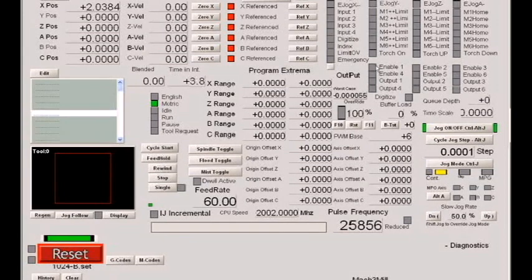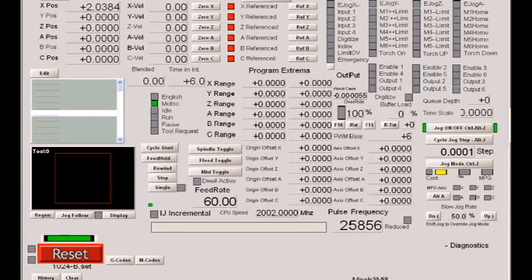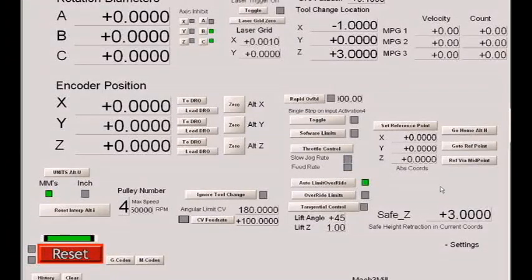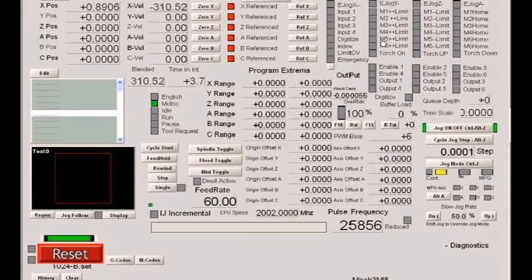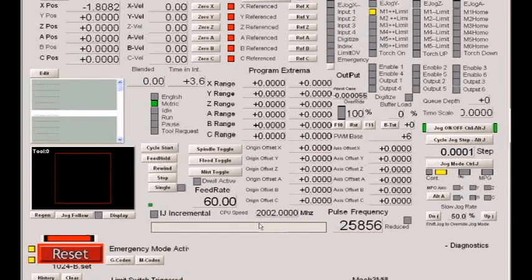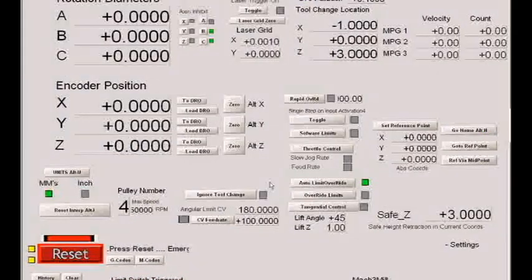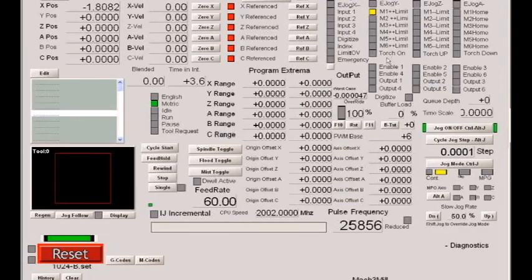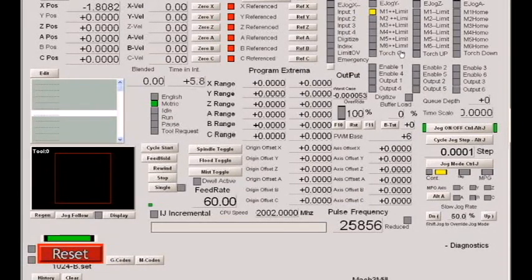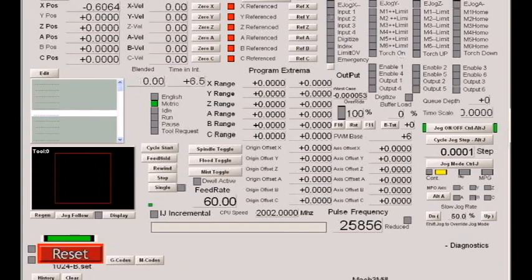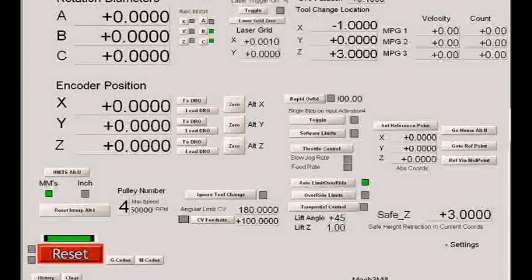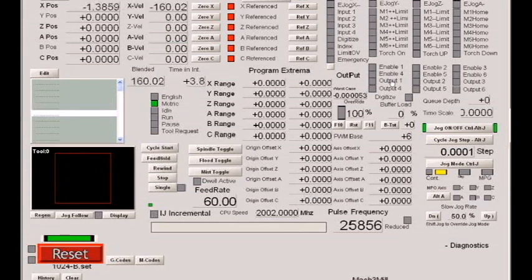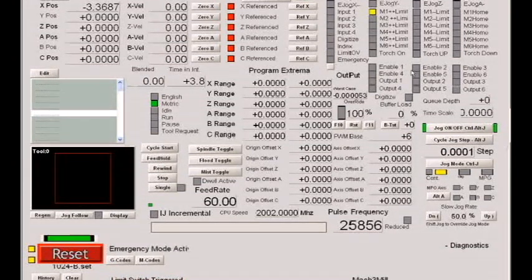There's also a selection that you can say auto-limit override. If you select auto-limit override and we happen to hit a limit switch, let's jog towards the switch, boom, we hit the switch, we're in emergency mode. In auto-limit override, the second you push reset, you automatically go into an override turning off the switch until such time as we drive off of the switch, at which time the overrides turn off, the switch is now active again. Should we drive on to the switch, we trigger a reset.